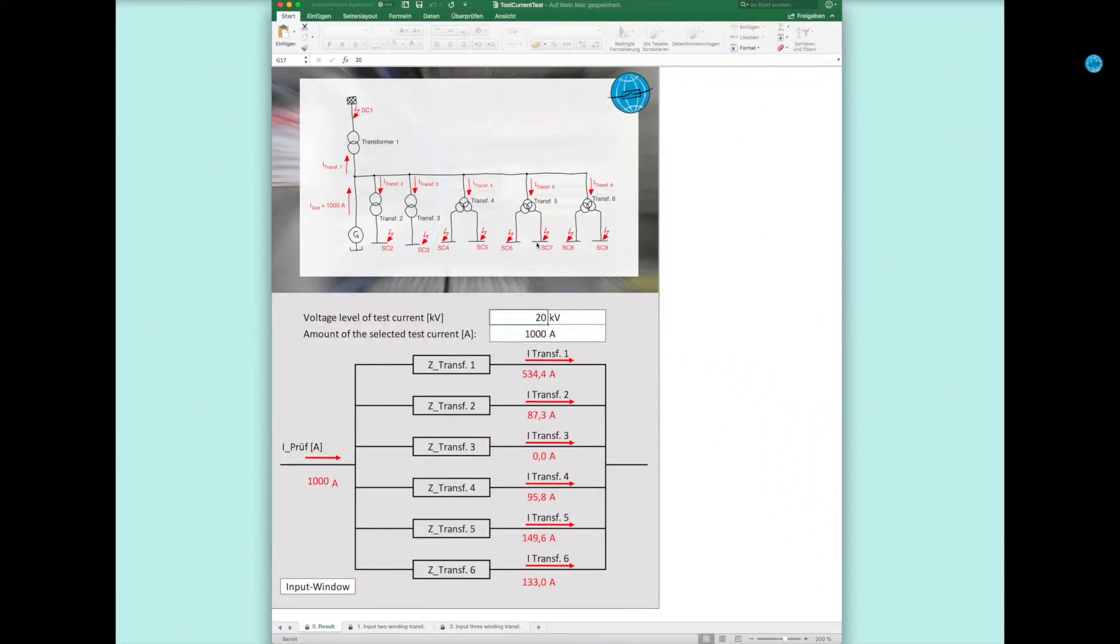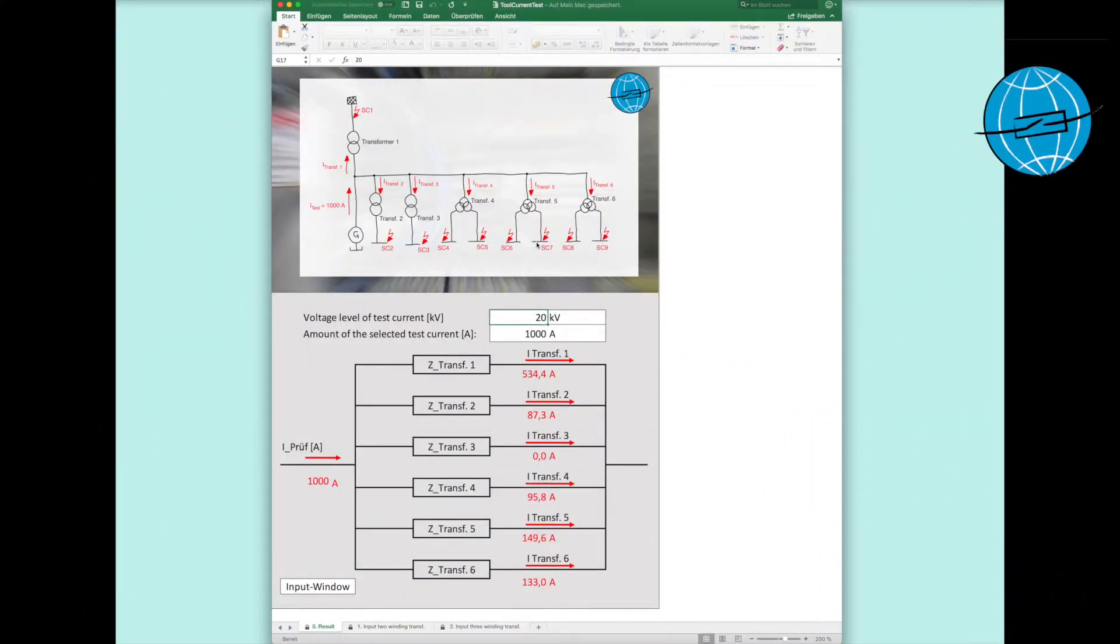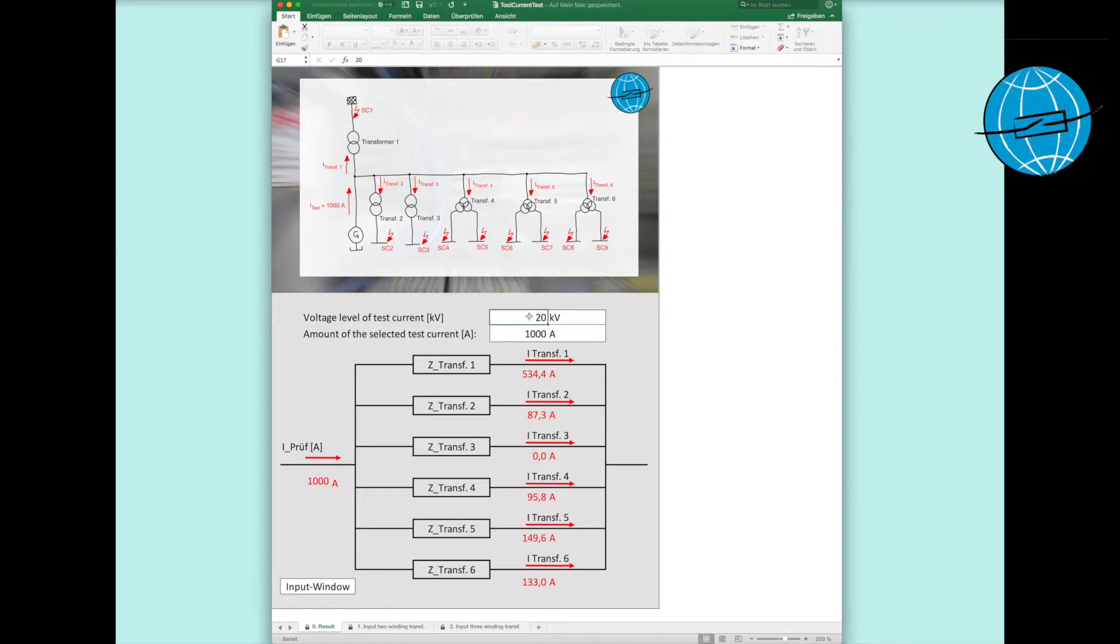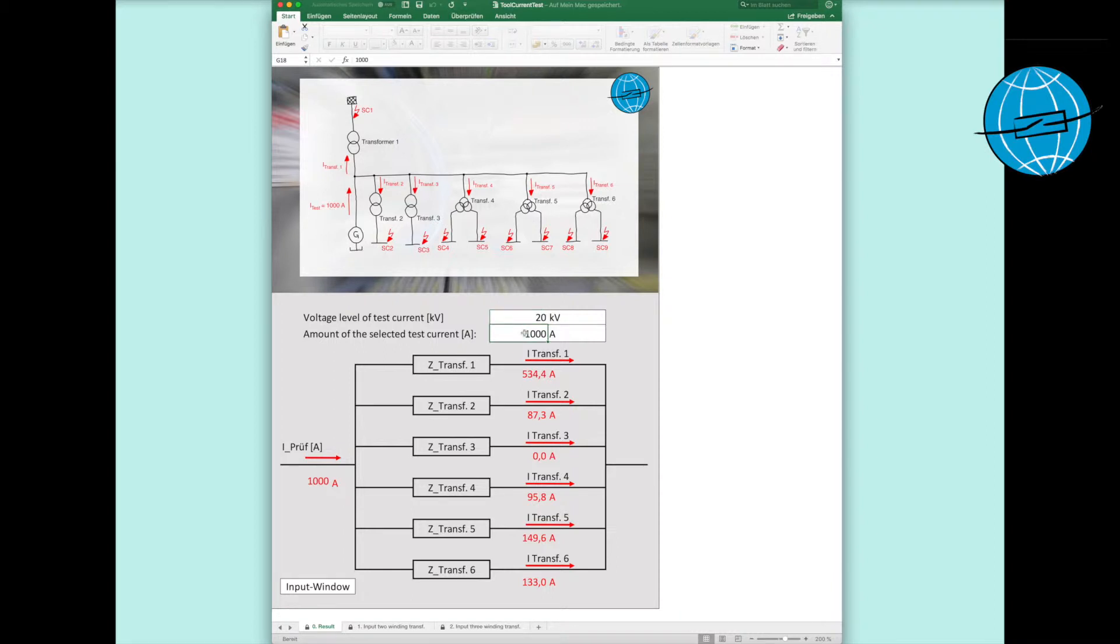As part of the current test run, we now have to calculate in advance how large the currents flowing through the transformers are. We start by entering the voltage. Here, the rated voltages of the transformers are meant on the faultless side at the voltage level of the injected test current. In our example, that's 20 kV.